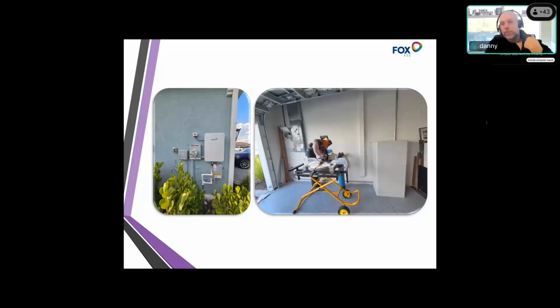Yeah, so 4 inputs, 3 MPPTs on the large units. And the first one needs to be parallel, so if you have 10 panels on one string, the other string on that first MPPT should also have 10 panels. It's always nice to match the same part of the roof too, if it's all on the south, east, or west roof, just try to match the same array if you can.